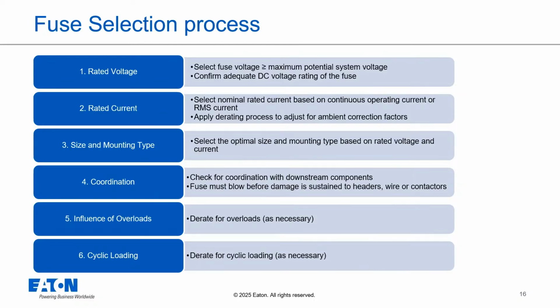Step 2, rated current. You'll select an initial nominal current rating based on the continuous operating or RMS current in the circuit. Crucially, you then need to apply a derating process. This adjusts the fuse rating based on environmental and operational correction factors. We'll dive into derating soon. Step 3, size and mounting type. Once you have the voltage and derated current requirements, you choose the physical size and mounting style that fits the application.